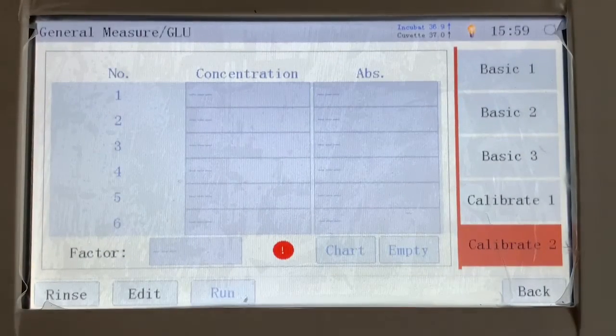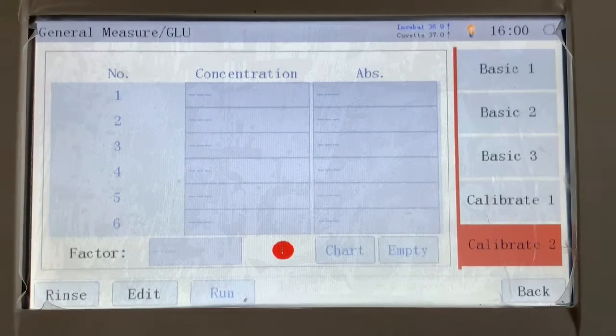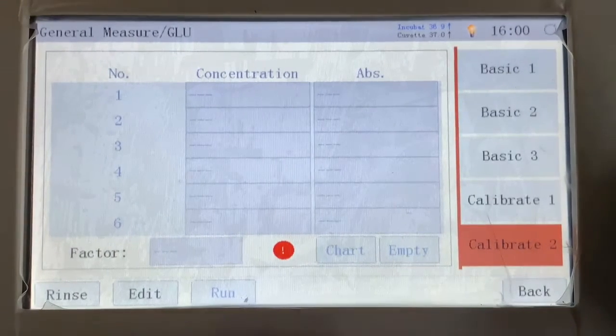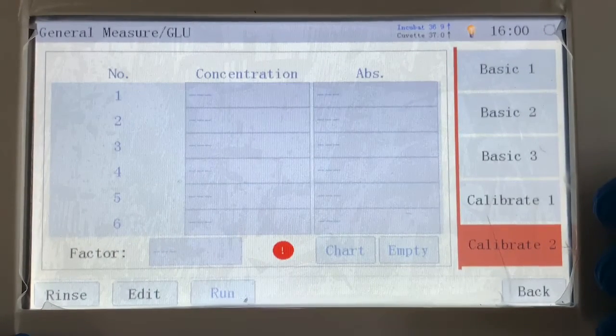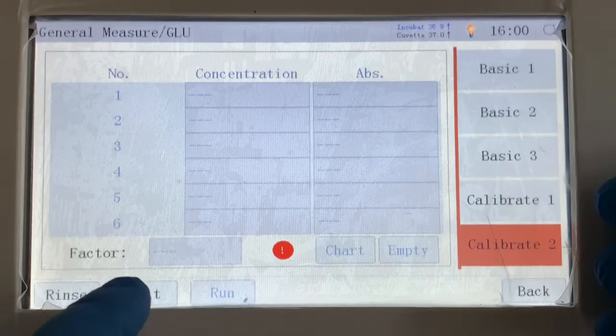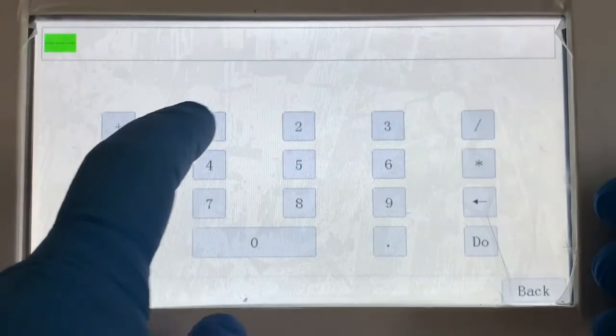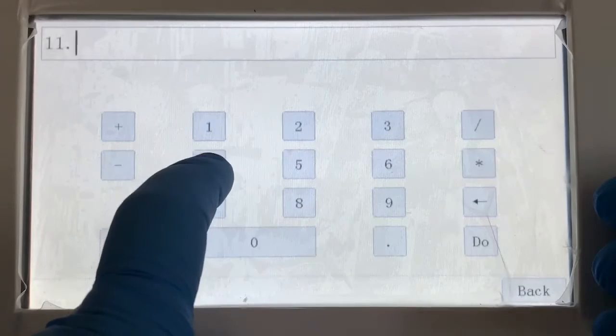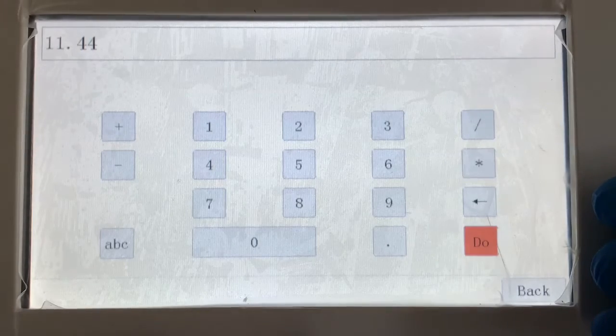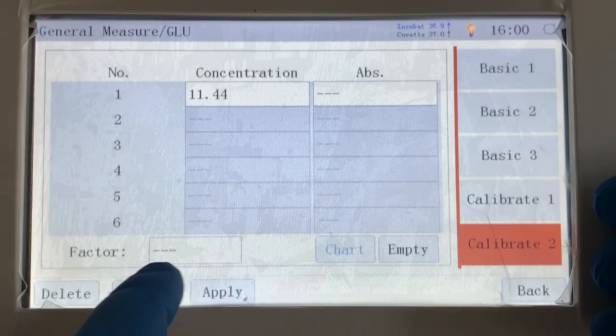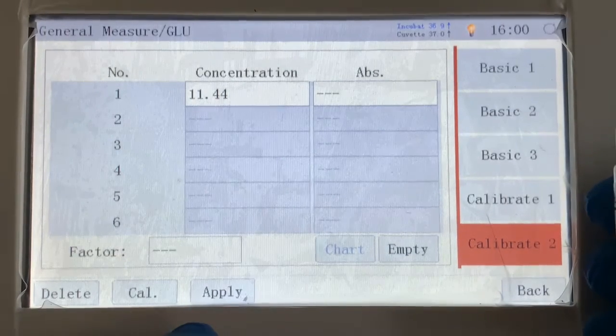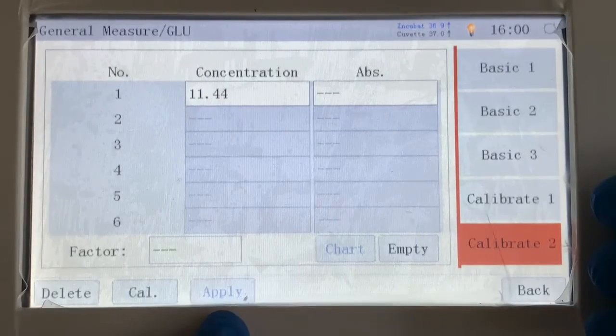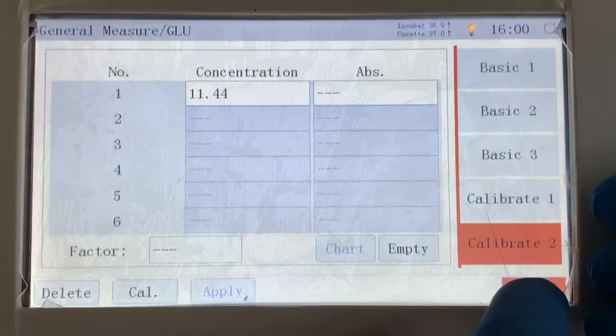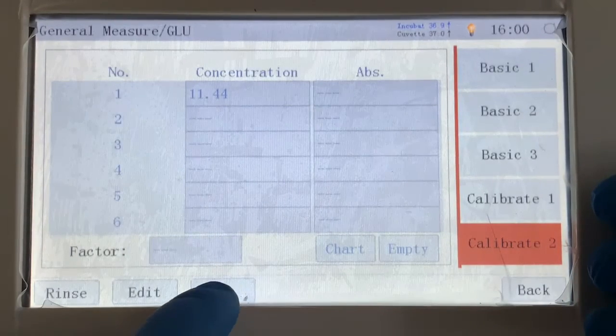To calibrate, we have to input the target value of the calibrator. In our case, the target value is 11.44. Click Edit. And leave the factor to be 0. Tap Apply to save, and tap Back, and tap Run.